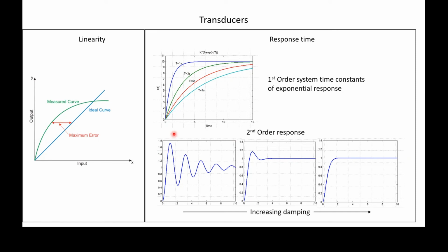And so that could be a problem if we have it bouncing a lot and the nurse says the systolic pressure, this peak here, is very high. But in fact, the blood pressure itself is not too high. And so that's why you'll see sometimes people erroneously put in a little bubble. And the bubble, of course, is air in the catheter system, and air is compressible and it acts to damp down that signal. So we talk about second order responses and we talk about damping them. The bubble is the wrong way to do it. There is another proper way of doing it that is sold, but we won't go into that.